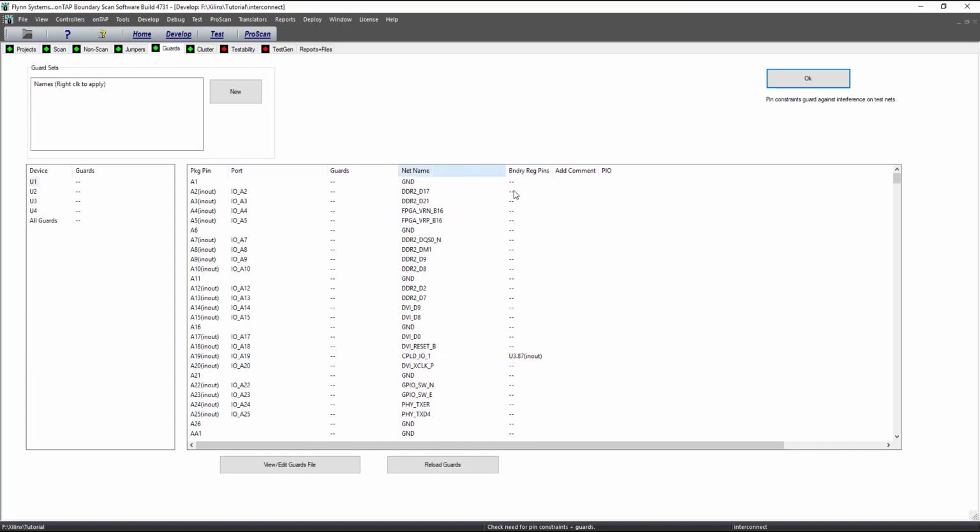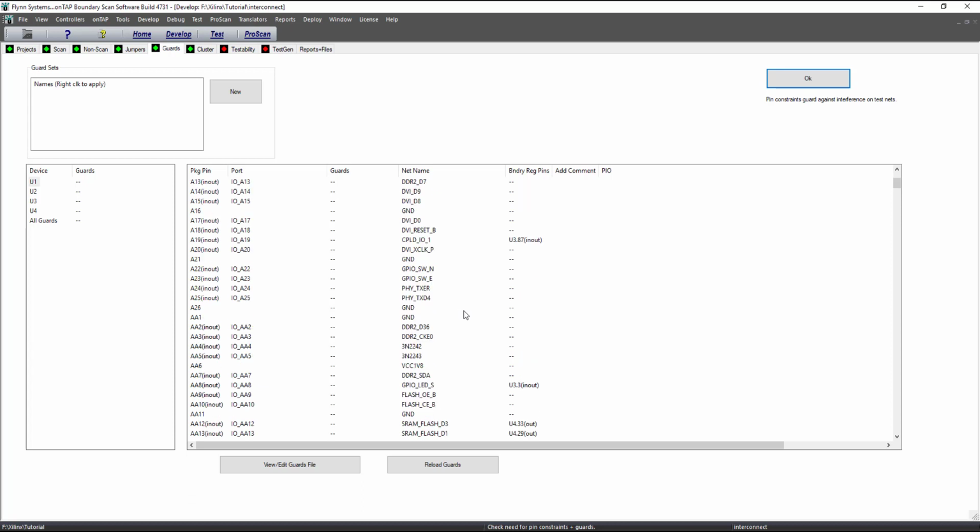we'll set a pin, and oftentimes it's helpful to look at the net names because sometimes they're a clue as to the type of pin it is. For example, here, flash output enable will be during the test, especially during the shorts test where there are a lot of pins switching. We don't want the outputs enabled on flash, memory devices, and other types of things.